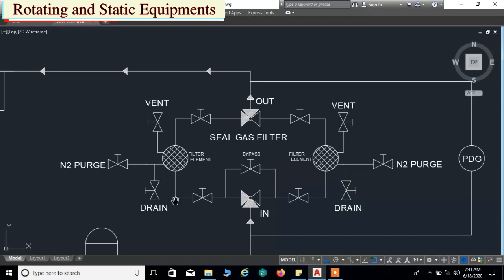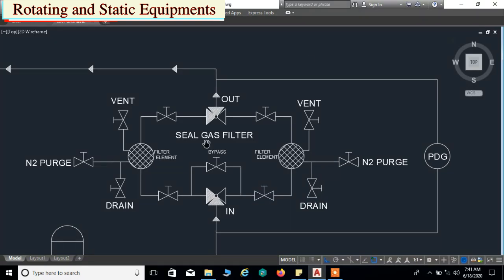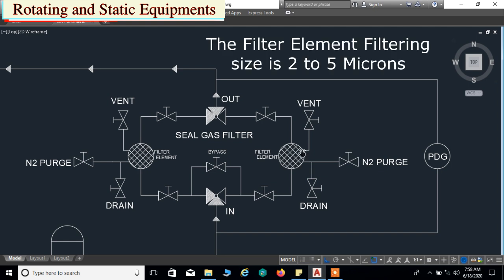This is a picture of a seal gas filter — it is a replaceable cartridge type twin gas filter. These filters are piped in a parallel arrangement using a continuous flow transfer valve. Normally one filter is online and the other is on standby. If the filter differential pressure gets high, the working filter element is choked and an alarm is shown from the DCS. We then need to change over the filter using the continuous flow transfer valve and bypass valve, after which we can replace the filter elements from the existing filter.